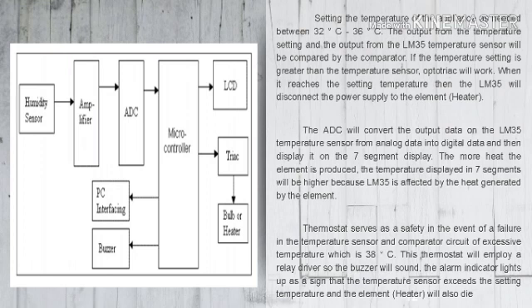The thermostat serves as a safety in the event of a failure. Temperature sensor and comparator circuit failure, with an exit temperature of 38 Celsius. This thermostat will employ a relay driver, so the buzzer will sound. The alarm indicator lights up as a sign that the temperature sensor exceeds the setting temperature, and the heater element will also turn off. Thank you.